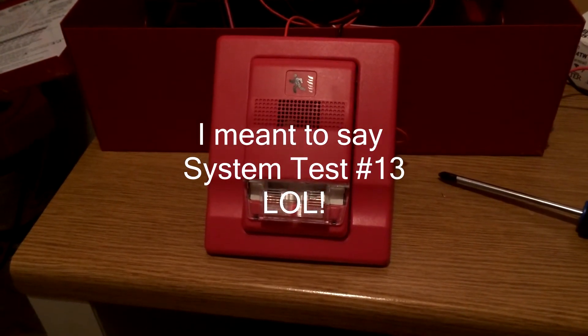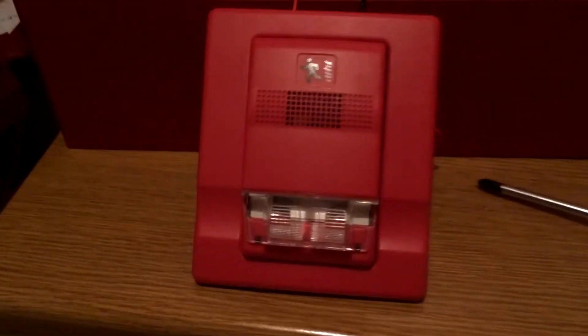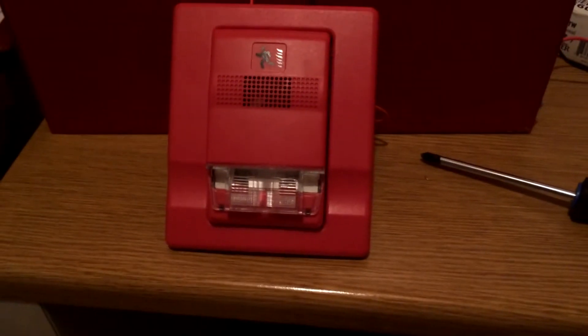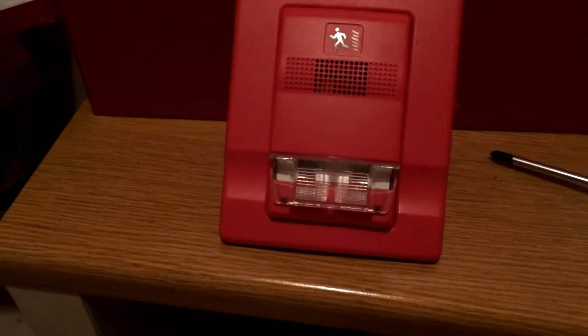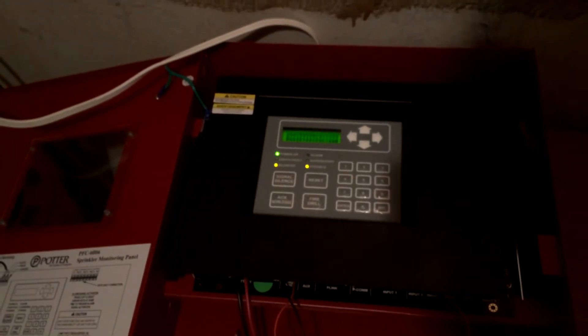System test number 13. Hi everybody, BigAlbDude707 here. This time I'm going to use an Edwards Genesis horn strobe. It's set on continuous and it's set at 15 candela — I don't know if you can see it there — so it can be efficient on the amp current. The panel only has one trouble which is low battery, which has no batteries.